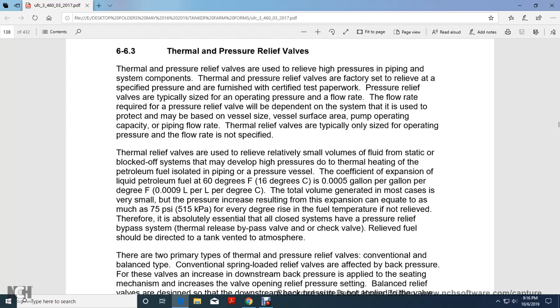Thermal pressure relief valves. Thermal pressure relief valves are used to relieve high pressure in the pipe and system components caused by thermal expansion. Thermal pressure relief valves are factory set to relieve at the specified pressure, with certified test paperwork.